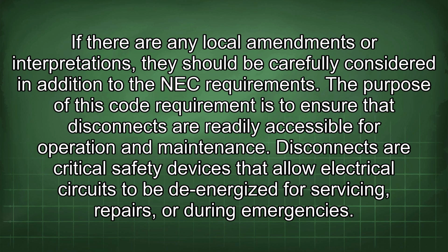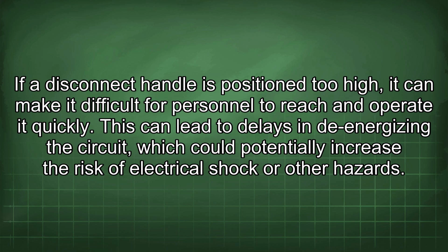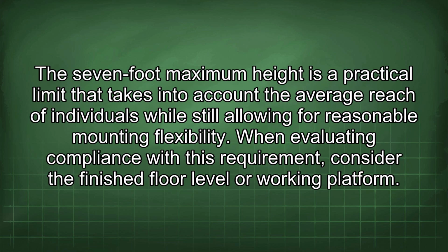Disconnects are critical safety devices that allow electrical circuits to be de-energized for servicing, repairs, or during emergencies. If a disconnect handle is positioned too high, it can make it difficult for personnel to reach and operate it quickly. This can lead to delays in de-energizing the circuit, which could potentially increase the risk of electrical shock or other hazards. The 7-foot maximum height is a practical limit that takes into account the average reach of individuals while still allowing for reasonable mounting flexibility.